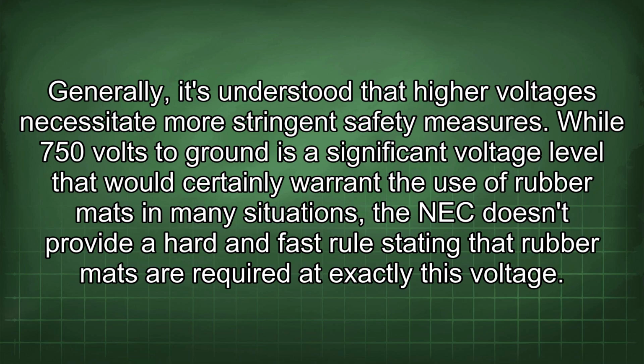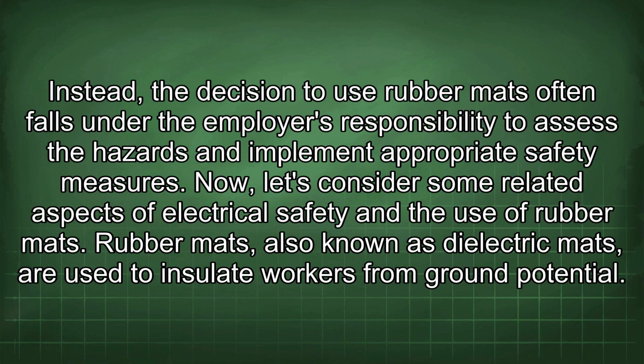While 750 volts to ground is a significant voltage level that would certainly warrant the use of rubber mats in many situations, the NEC doesn't provide a hard and fast rule stating that rubber mats are required at exactly this voltage. Instead, the decision to use rubber mats often falls under the employer's responsibility to assess the hazards and implement appropriate safety measures. Now, let's consider some related aspects of electrical safety and the use of rubber mats.